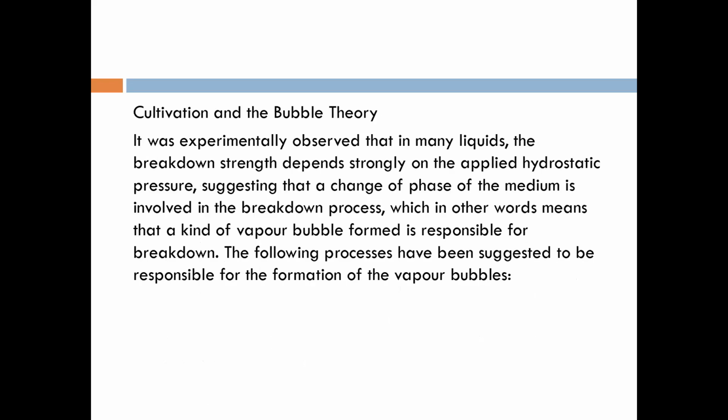Now, the second one, the cavitation and the bubble theory. Second method, or second theory, is going to be the cavitation and the bubble theory. It was experimentally observed that in many liquids, the breakdown strength depends strongly on the applied hydrostatic pressure, suggesting that a change of phase of the medium is involved in the breakdown process. It means the hydrostatic pressure will come, and the phase of the medium is also going to be considered, which, in other words, means that a kind of vapor bubble formation is responsible for the breakdown.